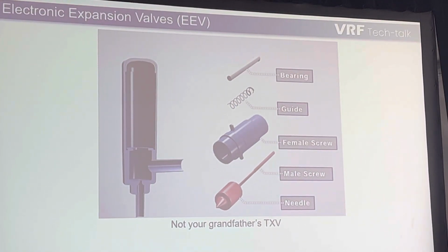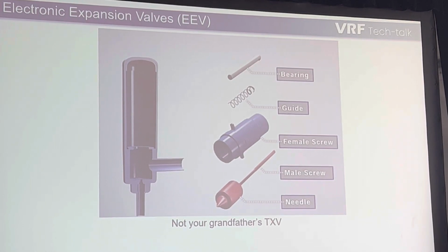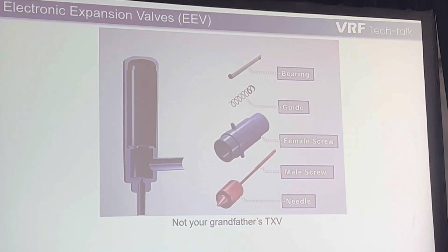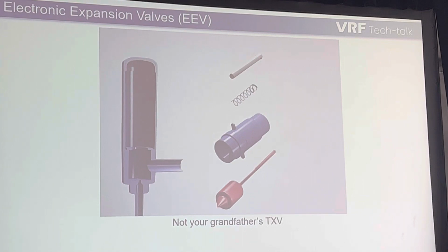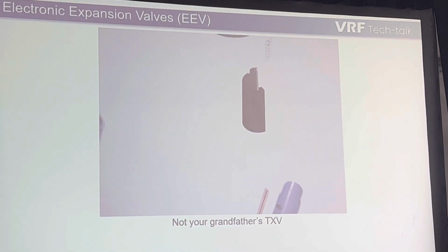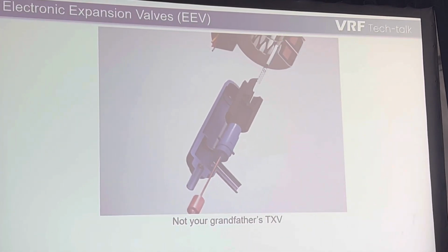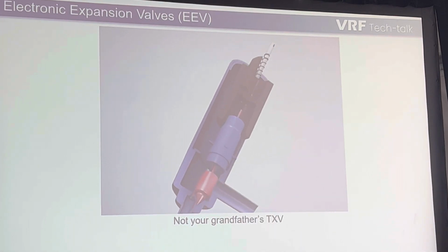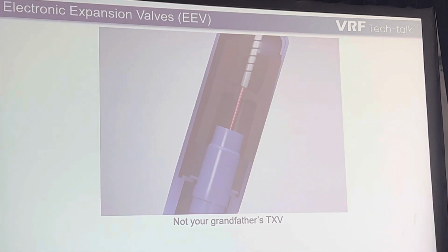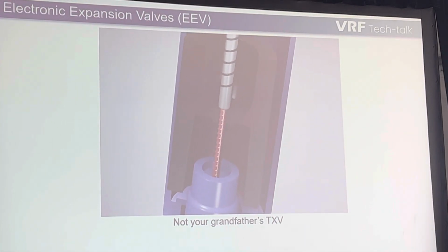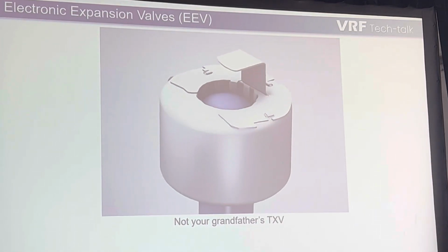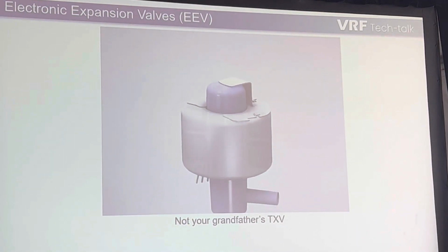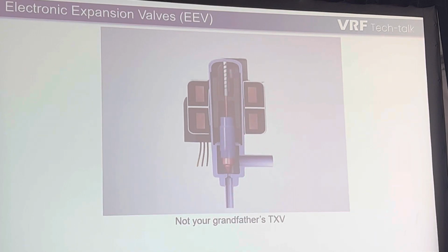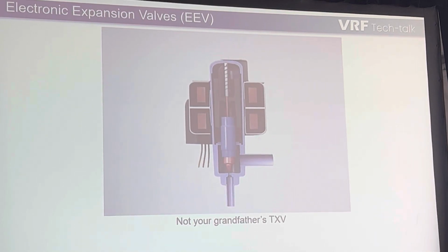Now notice, there are different sizes of valves like this. There is the 480 pulse, there is the 0 to 3,000 pulse, there is the 0 to 6,000 pulse. So you'll notice that they look slightly different. You also find these on your mini splits, your 1-to-1s and your multi-splits. You'll find this on some unitary equipment. Trane has been using them for a while, right? Carrier has a few, they're starting to implement it in some of their higher tier equipment. We've been using them since the dawn of time on all of our equipment. But this is how they operate.